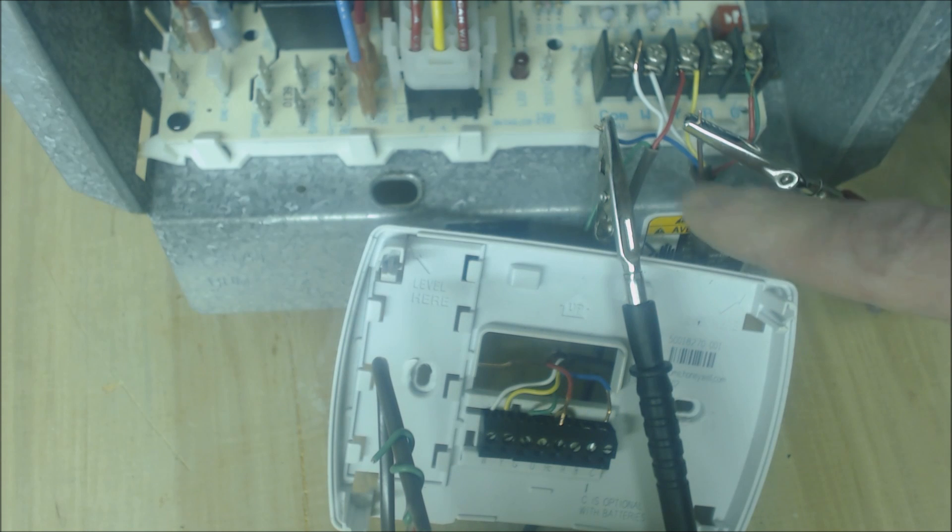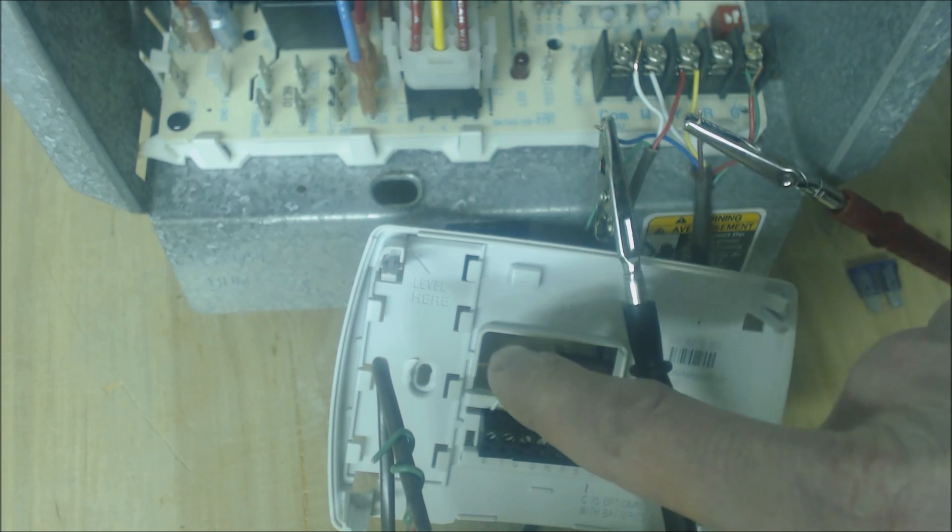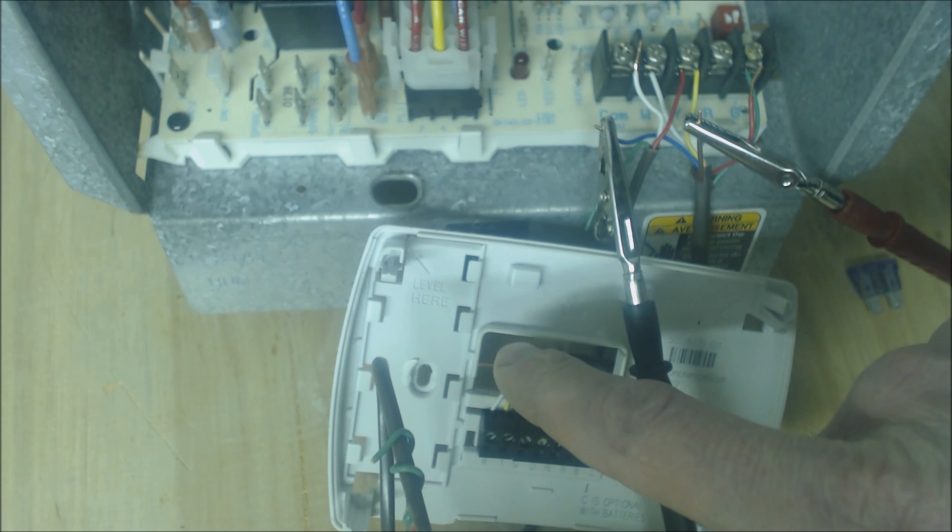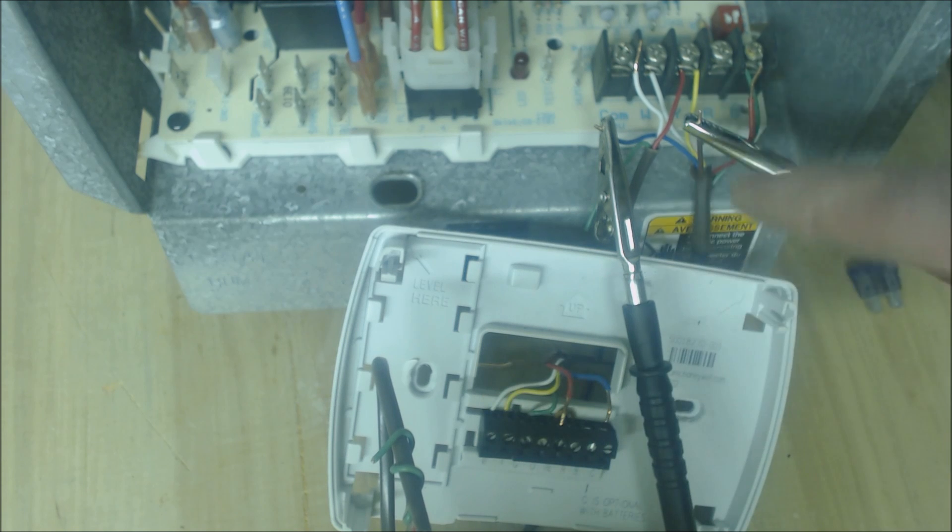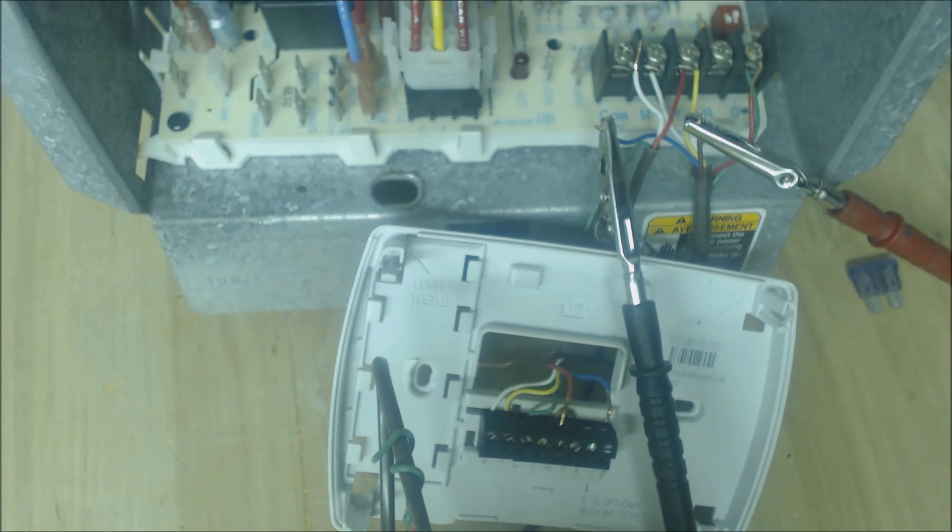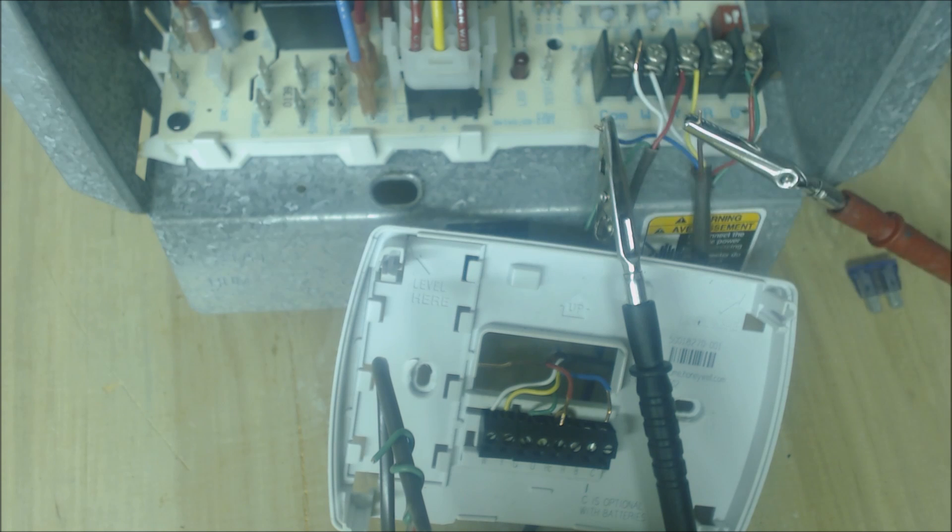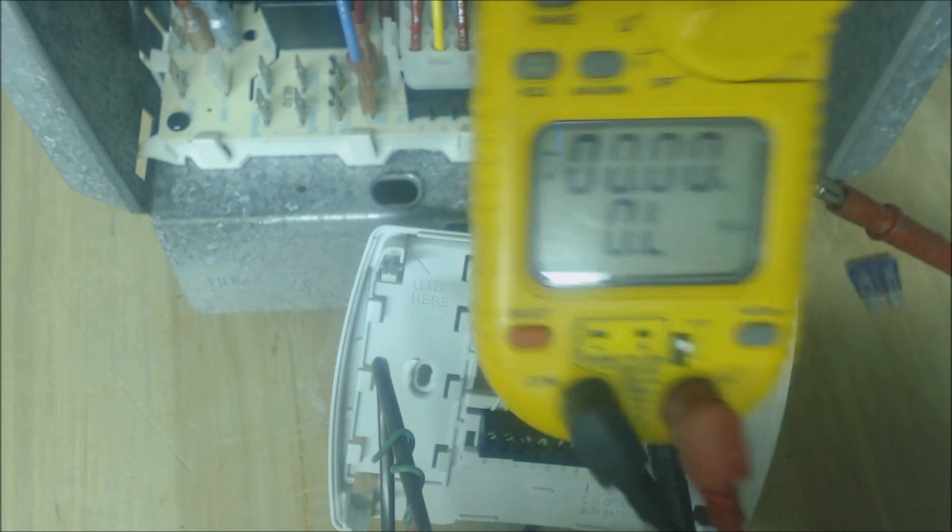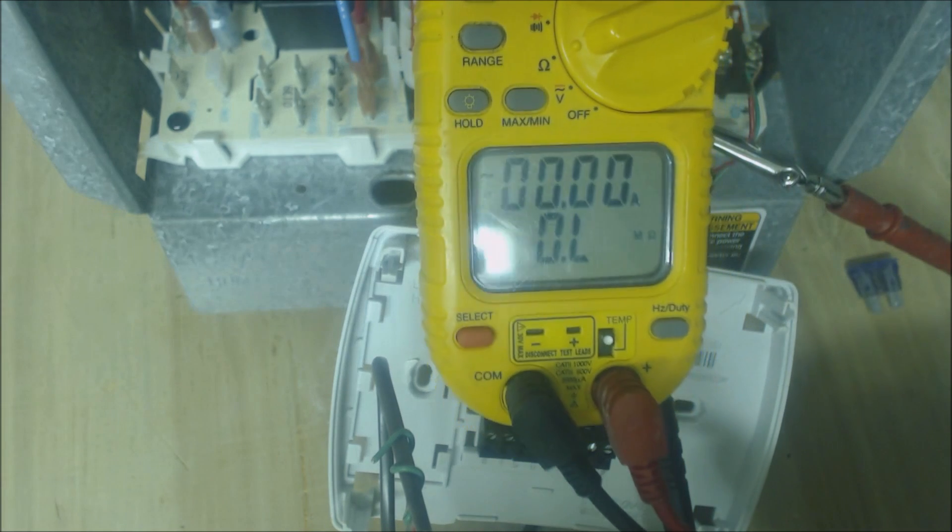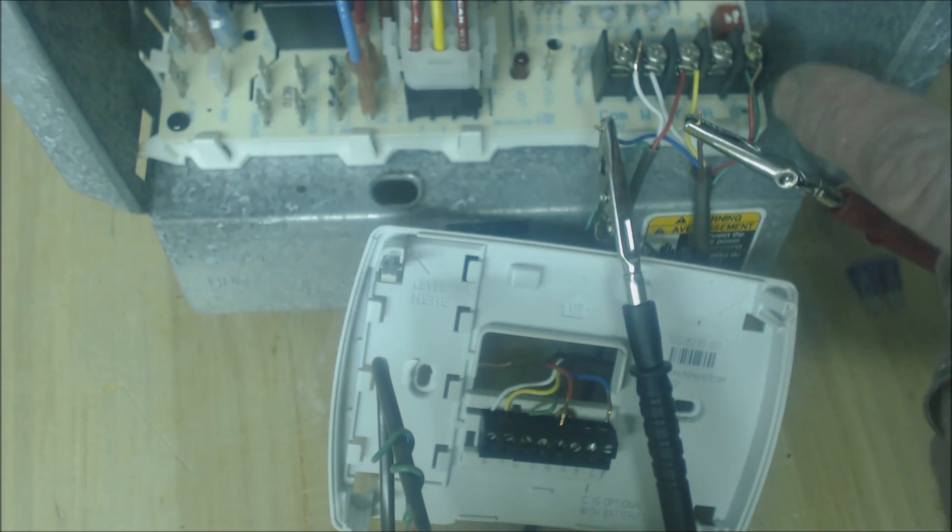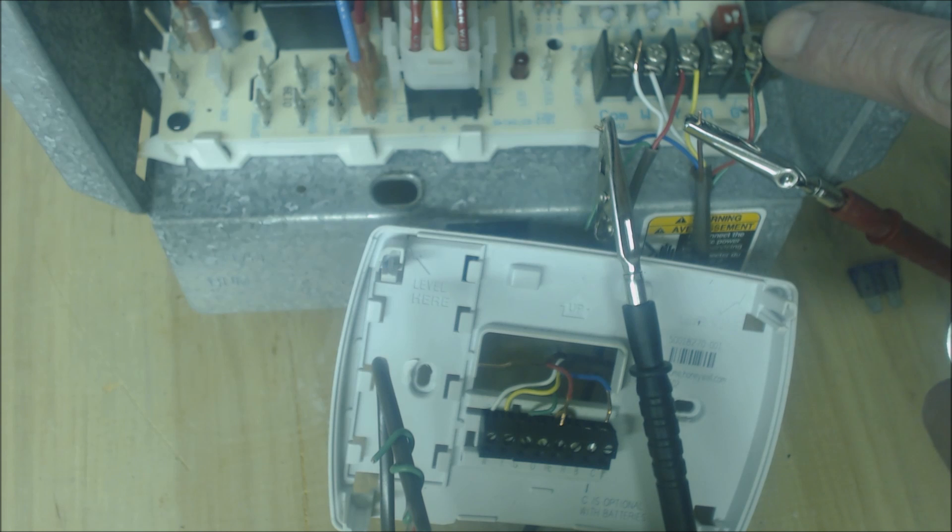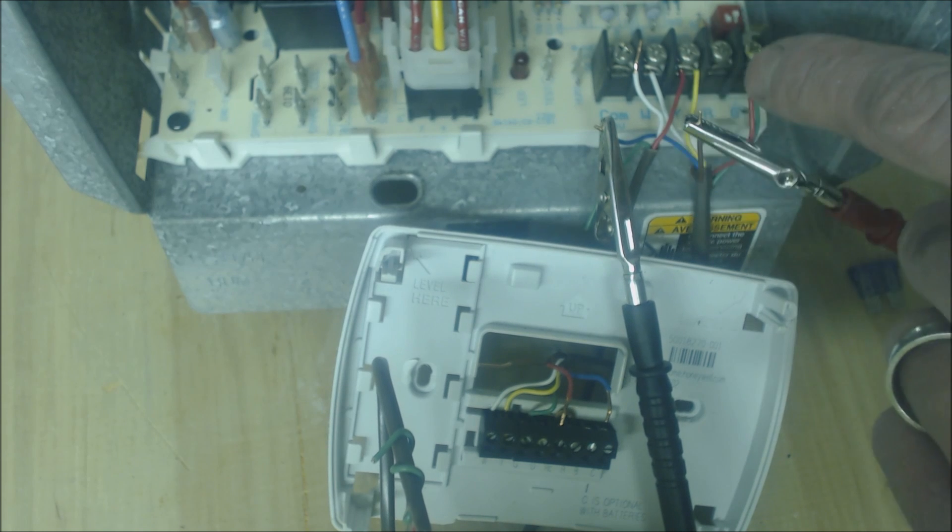Now we've pulled out the brown wire right here and we stripped the end and we pulled the brown wire out right here where your thermostat is. Right now we're going to check resistance between your brown wire and your blue wire. If that reads OL, which is what it does right now, then it is good to go ahead and switch out your red wire for your brown wire.